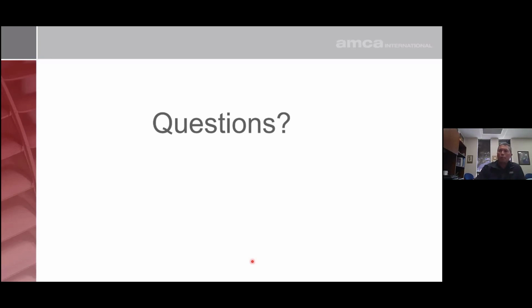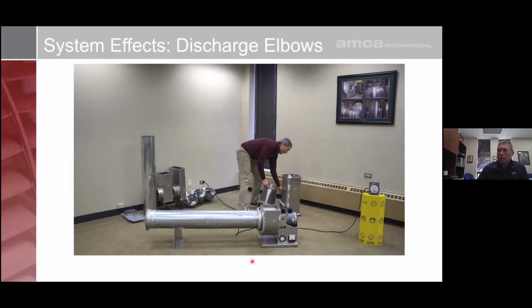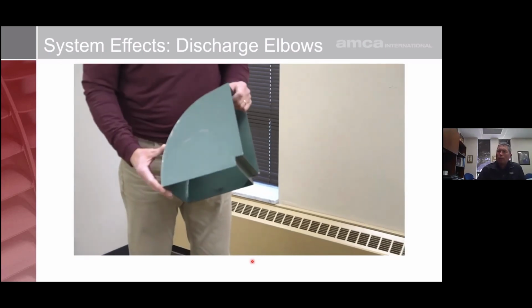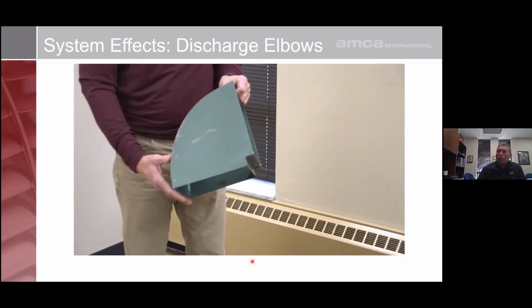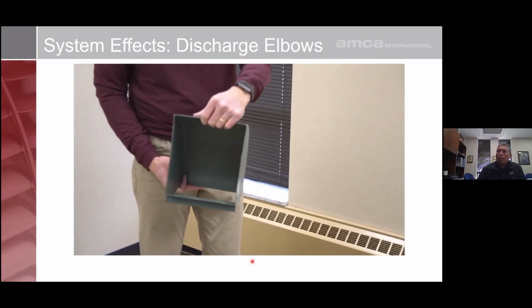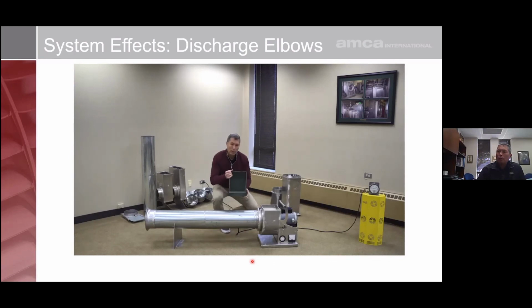Okay, moving on. Now oftentimes you have to have an elbow at the discharge of the fan. And if you have an elbow, like this 90 degree, there's a proper way to have the elbow orientated and there's an improper way. The improper way is to put it where it breaks the back of the air. The fan has a volute shape. Most of the air discharges on this side of the housing or the outside of the volute shape. And if we put an elbow that breaks the volute shape or goes against it, air pressurizes here, gets deadheaded, and has to get reaccelerated back out.